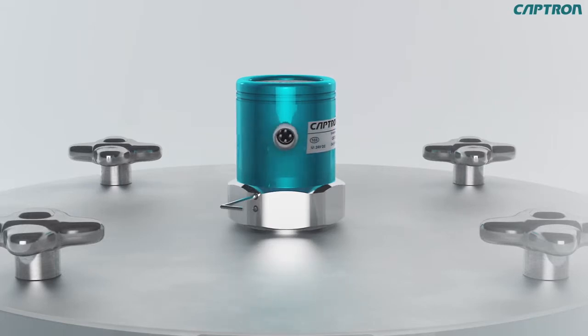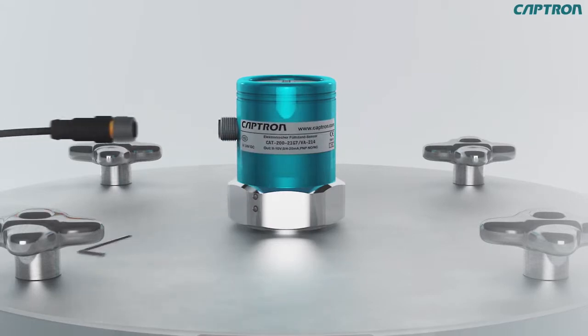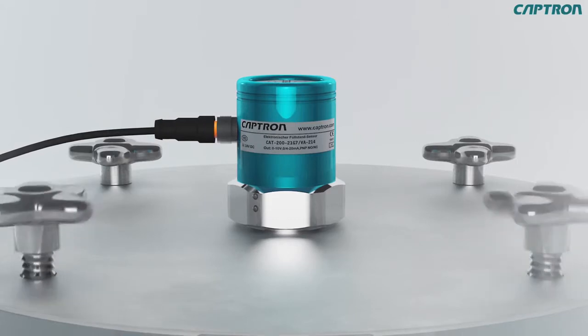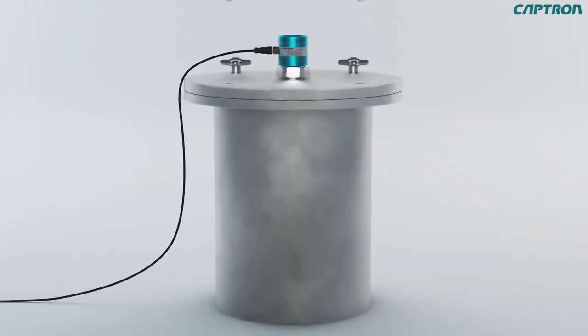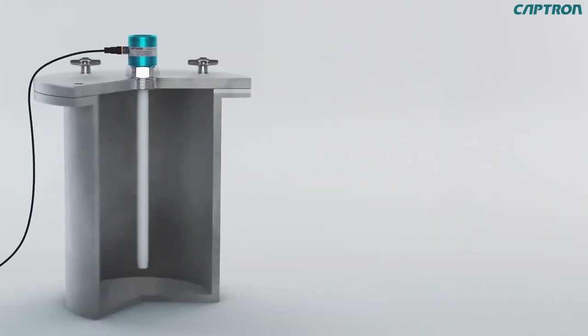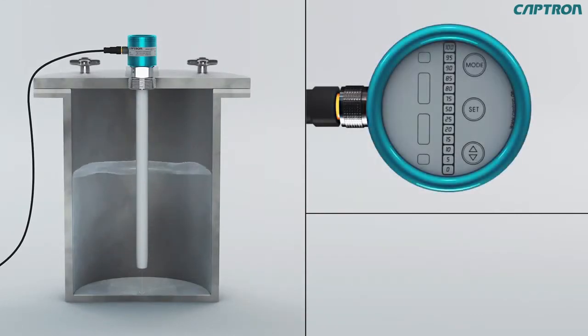Once the probe head has been optimally positioned, attach the M12 cable socket to the connector. Make sure that the probe tip does not touch the tank bottom during the installation. For the adjustment, we will now show you the control elements and displays of the VA214.